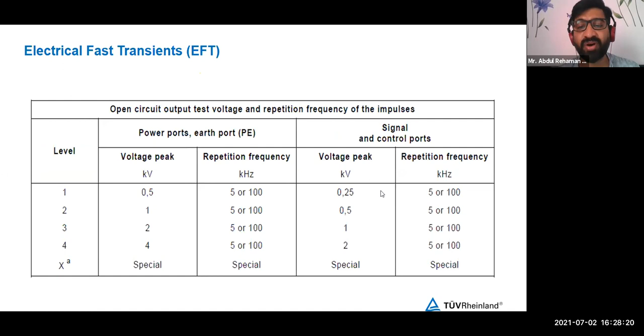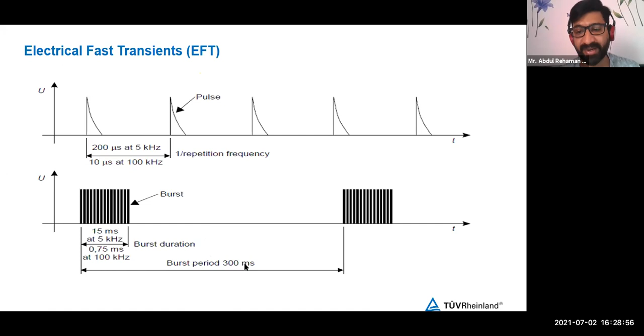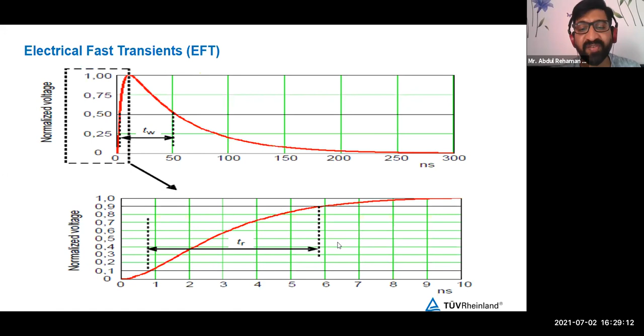This basically shows the pulses which are injected. When I say 5 kilohertz and 100 kilohertz noise, this is what we mean. These pulses together are called one burst, which is 15 milliseconds for 5 kilohertz, and for 100 kilohertz it is 0.75 milliseconds. The duration between these bursts is 300 milliseconds. This is the pulse shape of the electrical fast transients, where the rise time and the pulse width are important, where we say 5 by 50 nanoseconds.